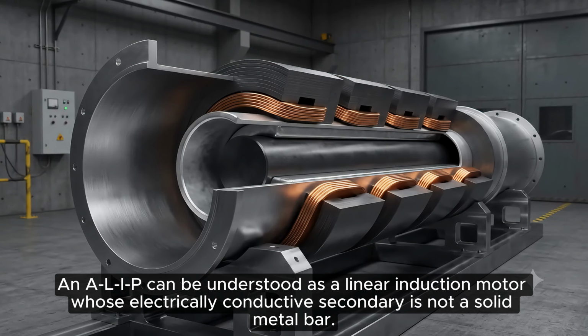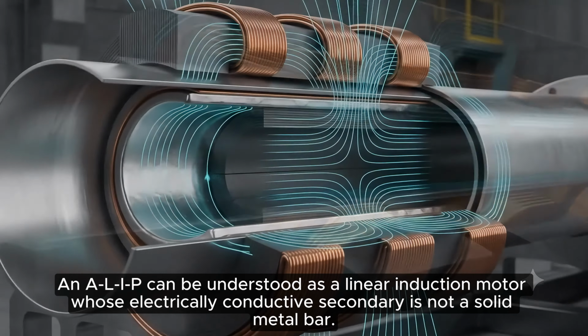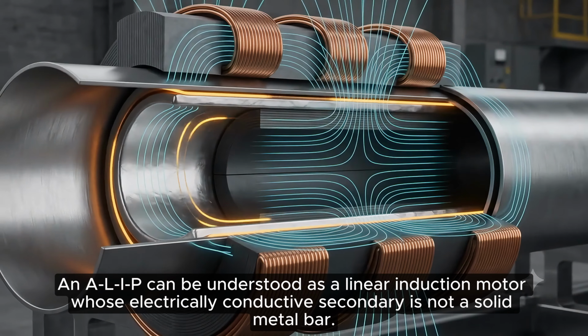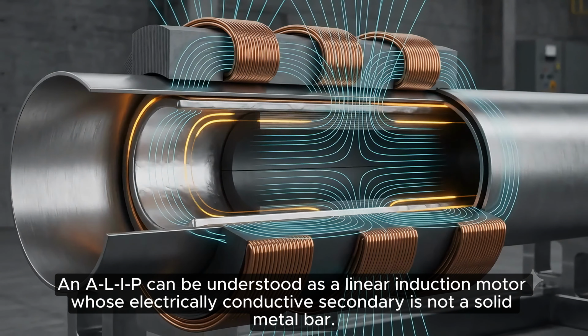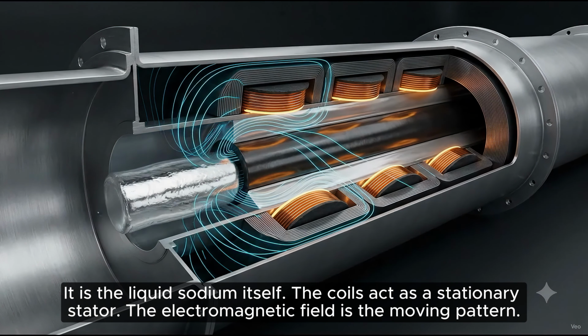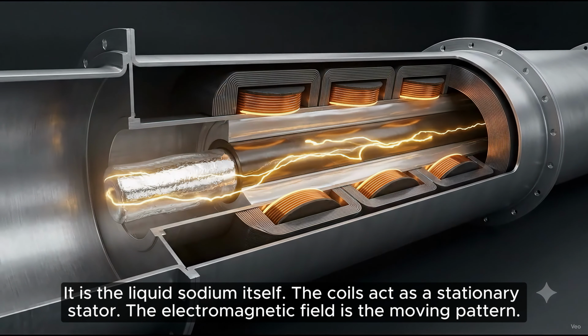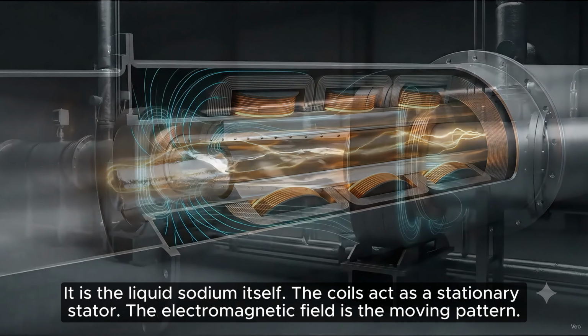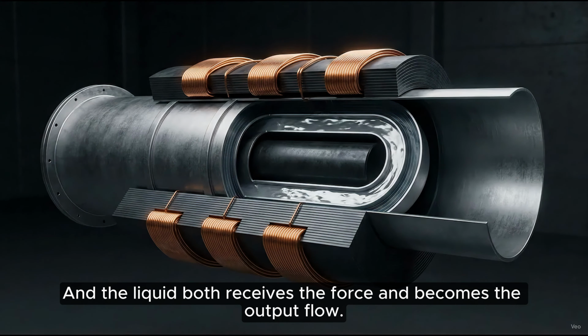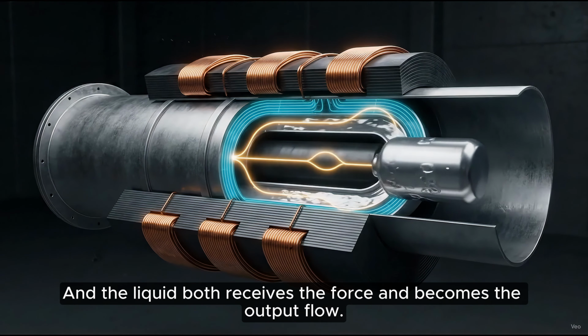An ALIP can be understood as a linear induction motor whose electrically conductive secondary is not a solid metal bar. It is the liquid sodium itself. The coils act as a stationary stator. The electromagnetic field is the moving pattern, and the liquid both receives the force and becomes the output flow.